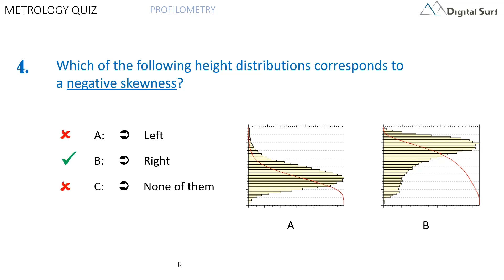The correct answer is B, the distribution shown on the right. The RSK parameter assesses the skewness of the profile, which is the asymmetry of the height distribution. This parameter gives information on the morphology of the surface texture. Positive skewness corresponds to high peaks spread on a regular surface — distribution is skewed towards the bottom. Negative skewness is found on surfaces with pores and scratches — distribution is skewed towards the top. It is therefore an interesting parameter when contact or lubrication functions are required. However, this parameter does not give any information on the absolute height of the profile, contrary to RA.